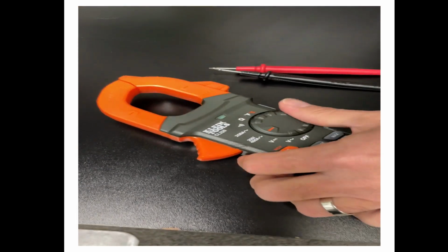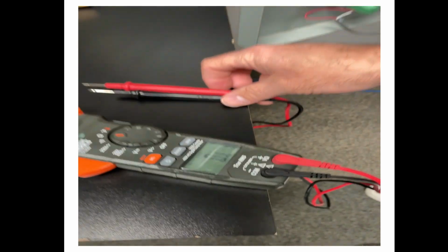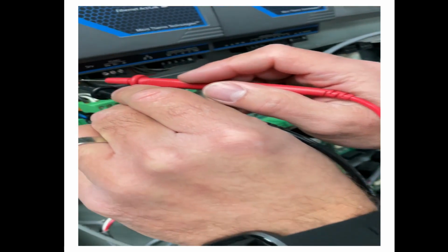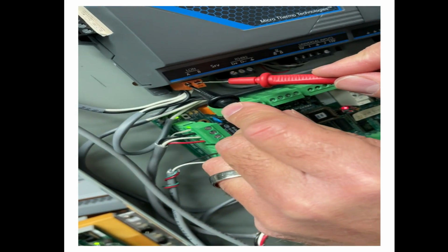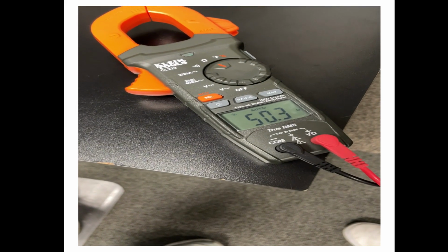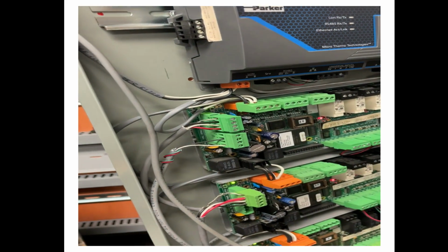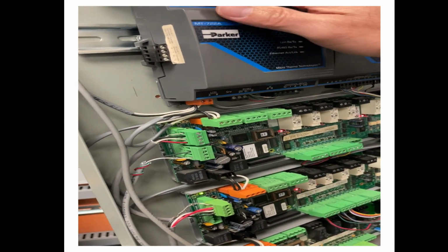Next, check the network resistance. On the orange network plug, check the resistance between the black and white conductors. In a supermarket, you should get a nominal 52 to 58 ohms, with ideal being 53 to 55.